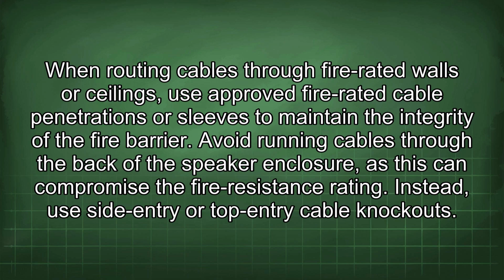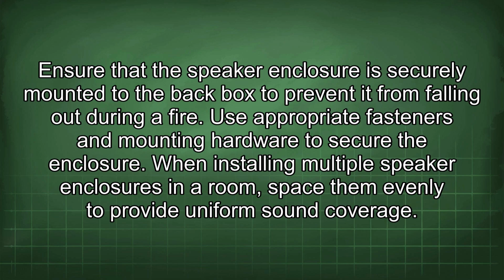Avoid running cables through the back of the speaker enclosure, as this can compromise the fire resistance rating. Instead, use side entry or top entry cable knockouts. Ensure that the speaker enclosure is securely mounted to the back box to prevent it from falling out during a fire. Use appropriate fasteners and mounting hardware to secure the enclosure.